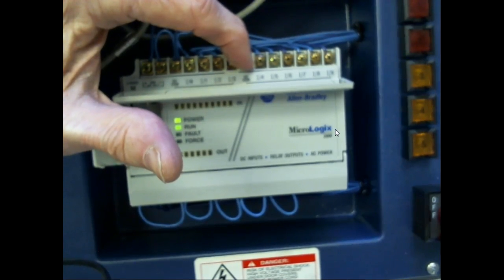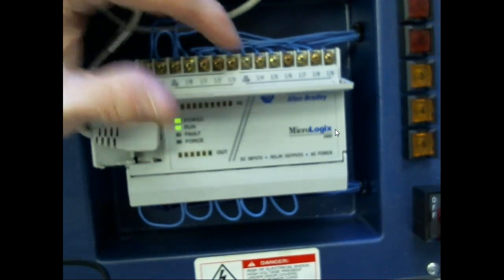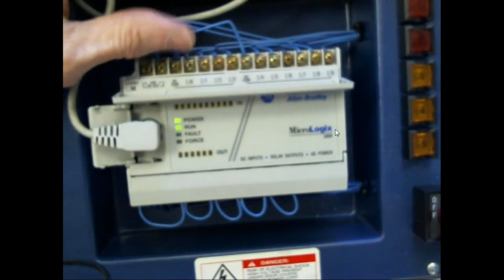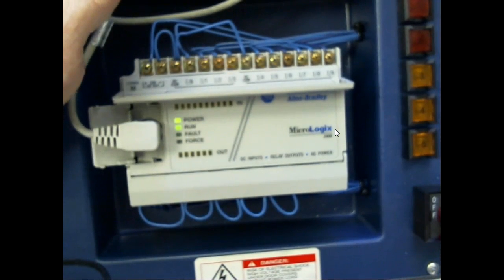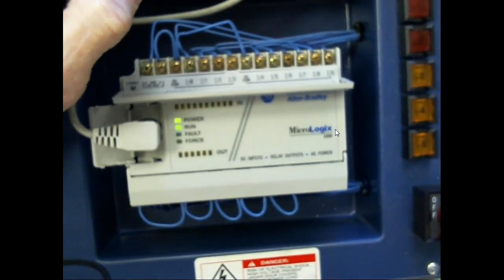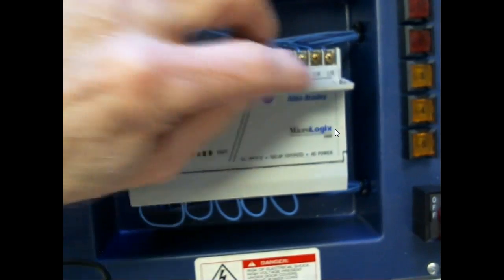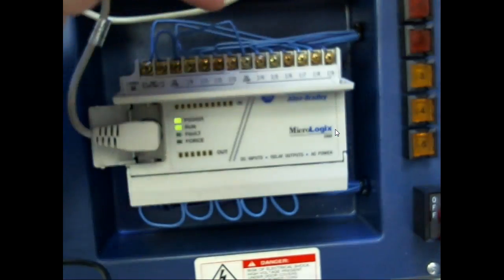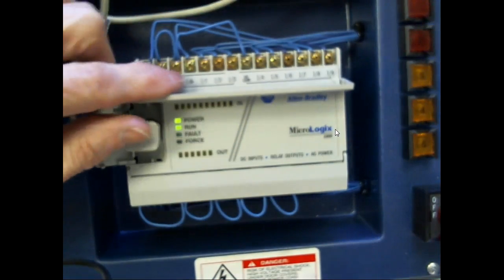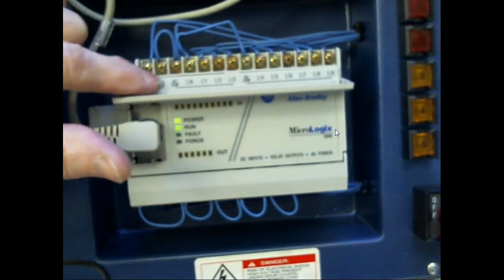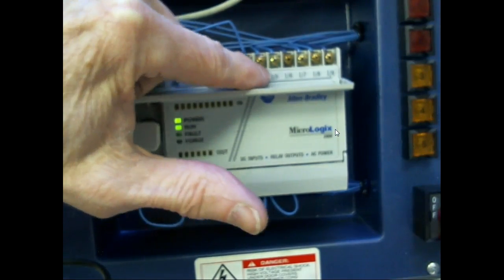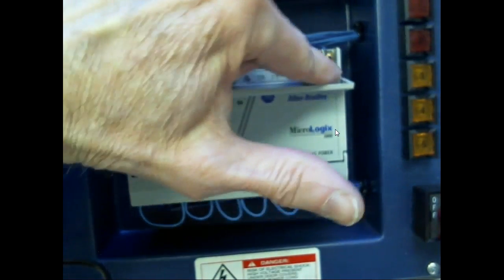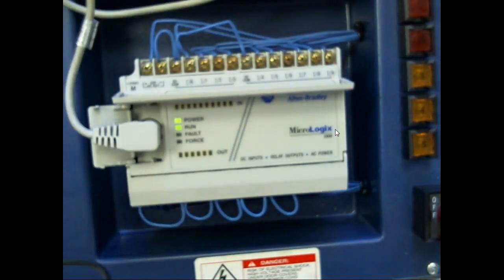So that means all my switches are set up to source. You can see what they did. Now, a lot of your fixed PLCs, you don't get this option, but Allen Bradley likes to do that. So that way you can, but it goes in groups, so you can't set them all up for sinking. You can't set them all up for sourcing. So these groups right here can be set up to either sink or source, and this group right here can be set up to sink or source. But you can't do all of them.